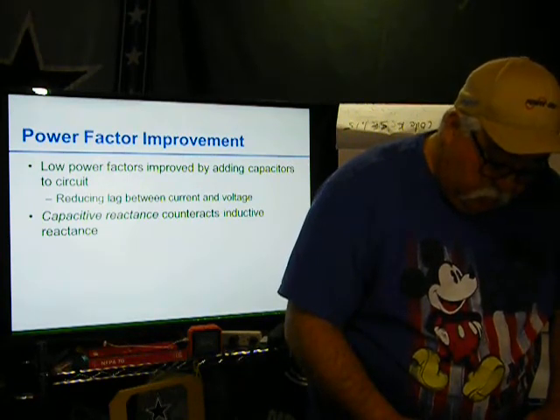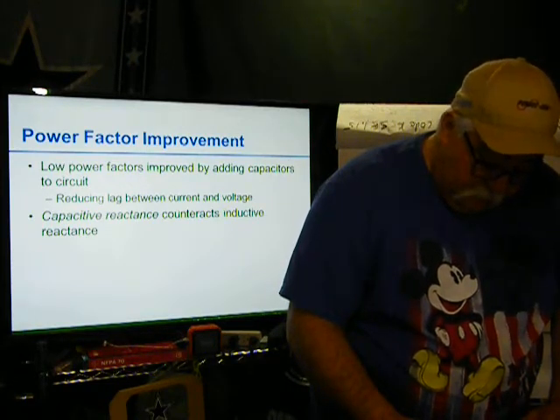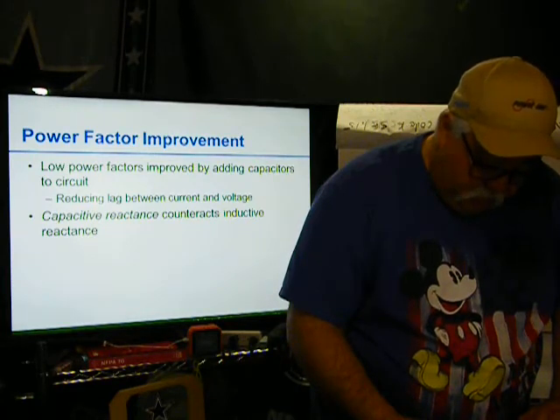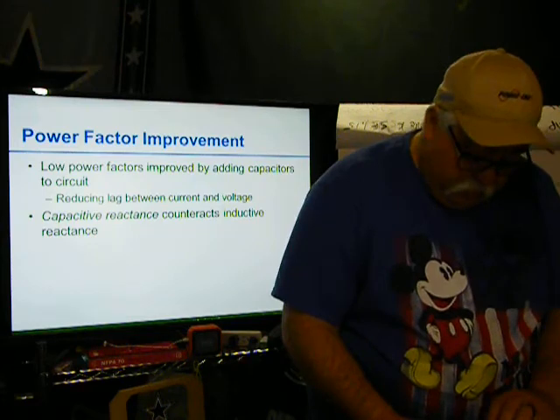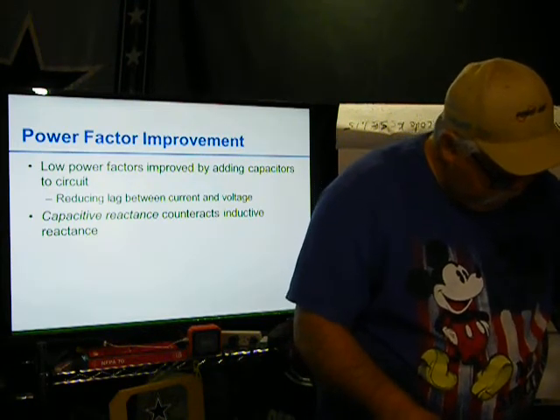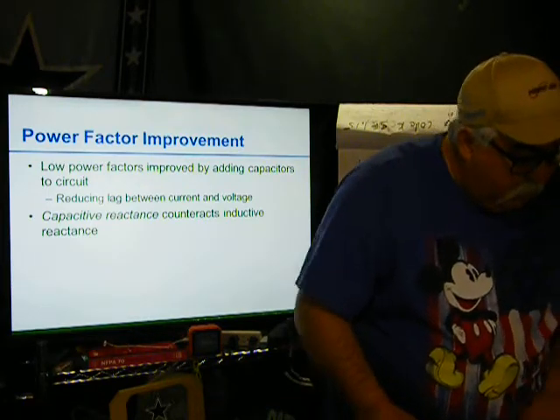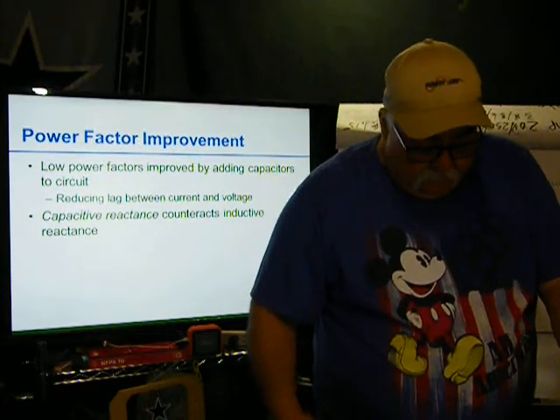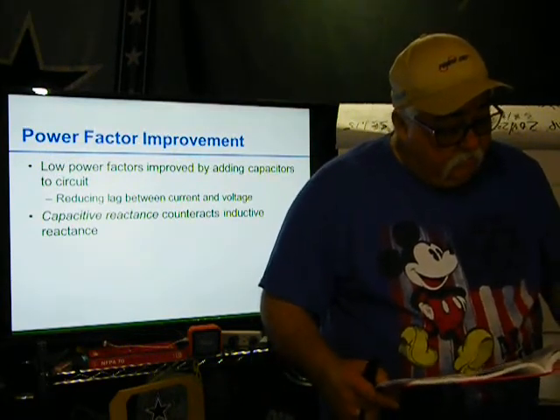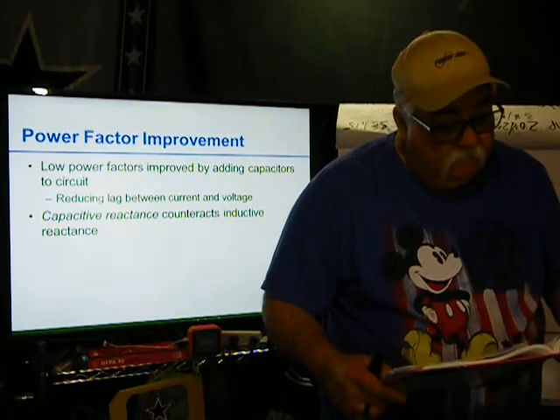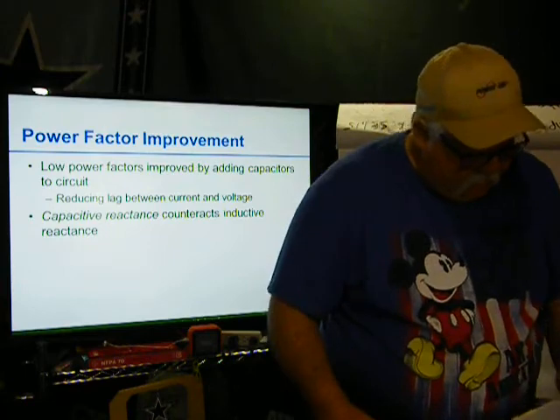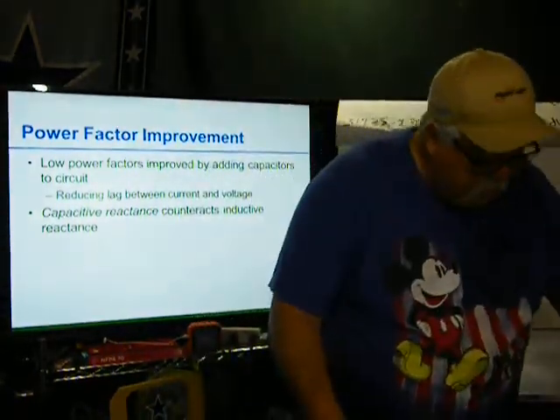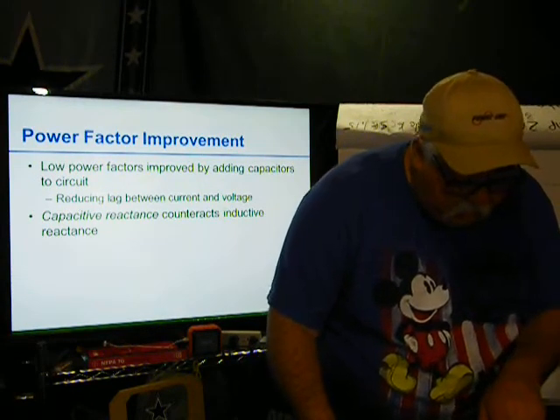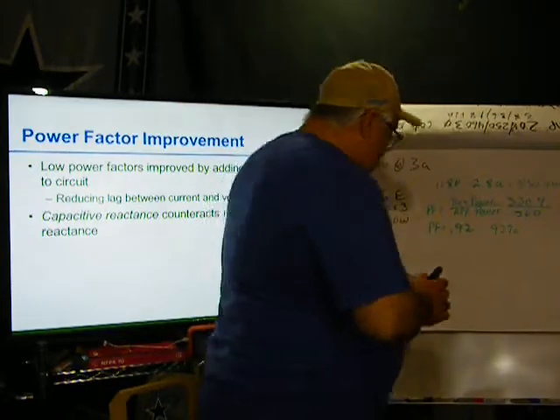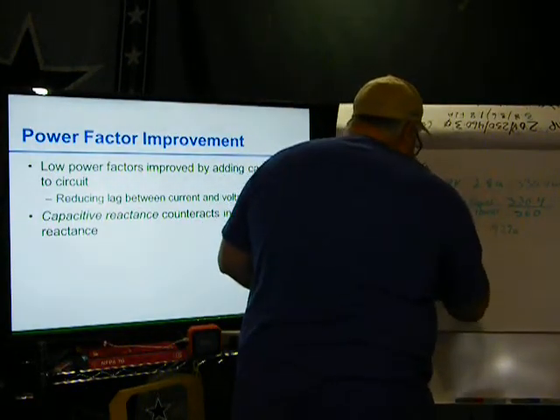To use a chart, first locate the existing power factor in the far left column, then the desired power factor. And multiply the number at the intersection of these numbers by the true power of the motor in kW to determine the capacitor reactance in kVAR. So I'm on page 198. I'm at 92%. Go to the left. Existing, I go to 92. Let's say I want to take it up to 100. So it's 0.392.